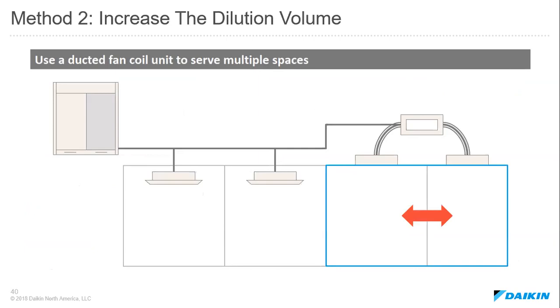Method two, we would increase the dilution volume. So in this case, going back to our first example, let's say that our first space was too small. We might use a ducted fan coil to serve multiple spaces. This then would increase our total dilution volume to the sum of the volumes of the two spaces as opposed to the singular space.